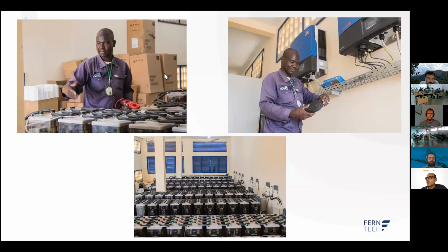And regarding the sizing - you're completely right, Paul, that you really need an exhaustive survey of what the load is going to be, in order to size not only the PV blocks but also the battery size. The battery is probably the most expensive component in the system, so you don't want to oversize it because otherwise it's going to be super costly. You really need a very detailed understanding of the future demand in order to correctly size the battery.